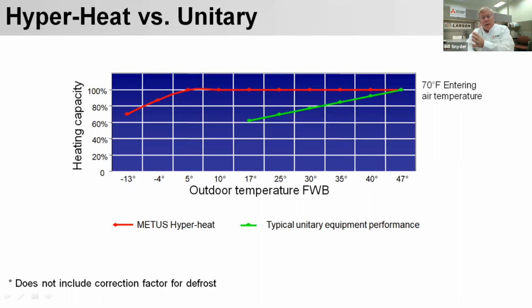So a typical heat pump, any heat pump, will give you what they call its 100% rated capacity at 47 degrees. So if we had, for instance, a 3-ton, 36,000 BTU heat pump, it would give you 36,000 BTUs at 47 degrees, and at 17 degrees it's typically about 60% of that capacity. So a 36,000 BTU heat pump at 47 degrees, the typical one at 17 degrees is going to give you about 21,600 BTUs.